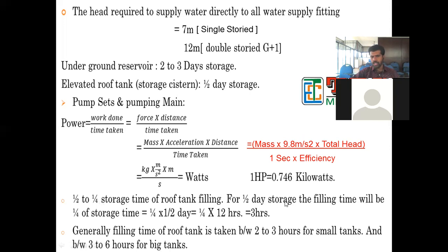Like for a half day storage, half day means it is 12 hours. If you are taking a half day storage or a 12-hour storage, the time taken to fill it, you can take 1/2 to 1/4. So if you are taking 1/4 of the storage time, half day means 12 hours, correct? So 12 into 1/4 of the storage will be 3 hours. Normally it will be in the range of 2 to 3 hours to fill the tank.